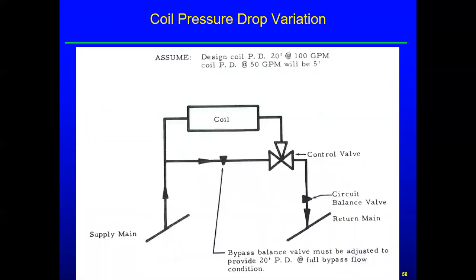So what this shows is obviously just one coil, one unit. But let's say that the design pressure drop was 20 feet at 100 GPM. Well, say that valve modulates, and we're going to get half of the flow through the coil and half of the flow through the bypass, which means you have half of the velocity through the coil and half of the velocity through the bypass, which means you have 25% of the pressure drop. So now that whole circuit from supply main to return main only has 5 feet, where at full flow, either through the bypass or coil, it has 20 feet. As that valve modulates, that pressure difference is going to cause upset in the system and potentially upset other coils and other zones that are on the system as well.